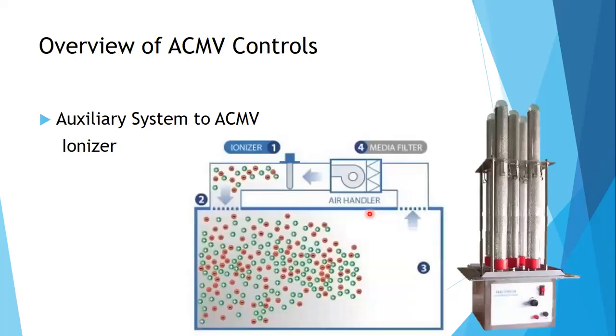Another system is the ionizers. Just like the UV light, the ionizers ionize the air so that the dirt and the bacteria die and are clumped together, so that they will be big enough to be captured by your filters. So ionizers release negative ions so that the dirt, the bacteria and the viruses within the air will be clumped together and will be captured by your media filters or your filters.